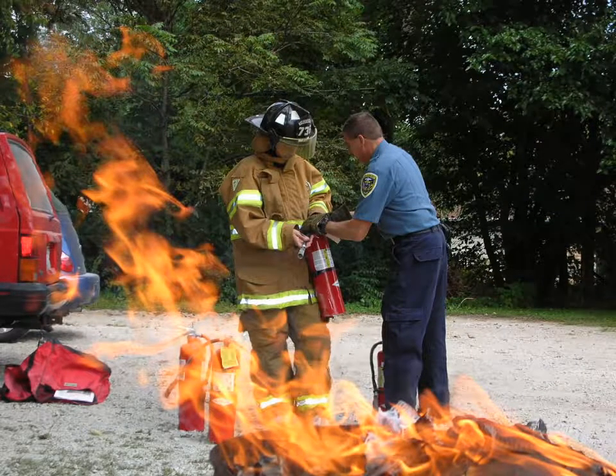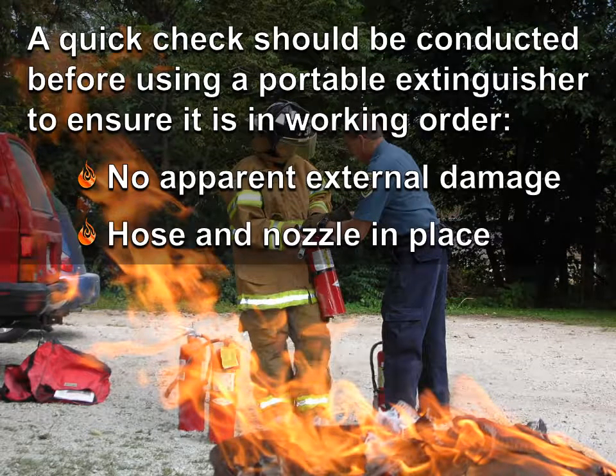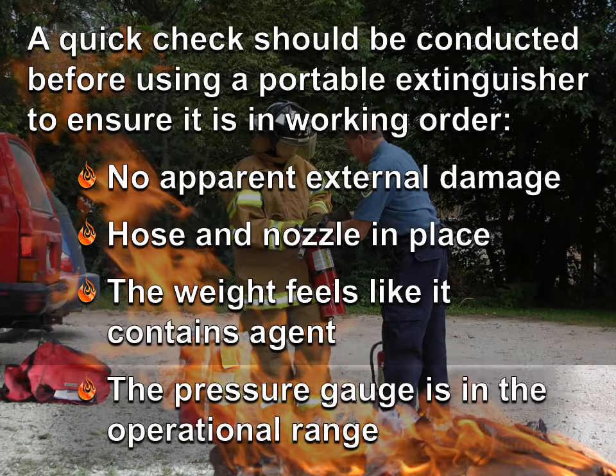A quick check should be conducted before using a portable extinguisher to ensure it is in working order. Make sure there is no damage to the outside of it. The hose and nozzle are in place. The weight feels like it contains agent, and the pressure gauge is in the operational range.